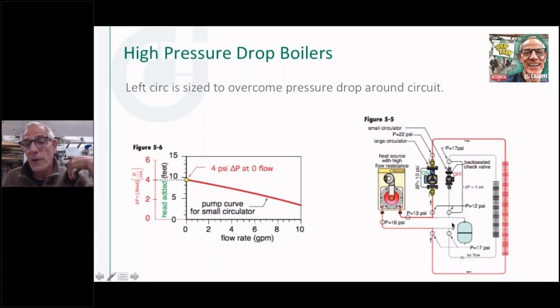So if you look at all the pressures here, notice here's our point of no pressure change. So we've pumped this thing up to a 12-pound static fill pressure. And now we're going to switch on this high head circulator. And you'll see that we immediately are adding 10 pounds of pressure differential across that circulator. So now we've gone from the 12 pounds to 22 pounds at the discharge gauge. Go around through the circuit here. Obviously, as we go through the piping and the fittings and the heat emitters and everything else, we're going to scrub away or use up some of that delta P that the circulator imparted to that circuit.